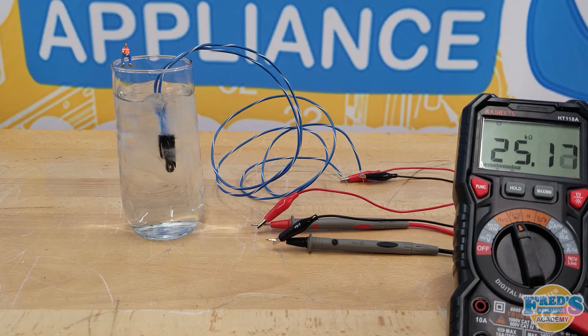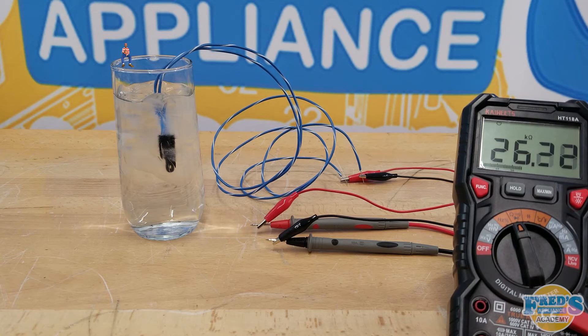If the resistance value of the thermistor is open, shorted, or out of range by more than 10% at any time during this test it should be replaced.